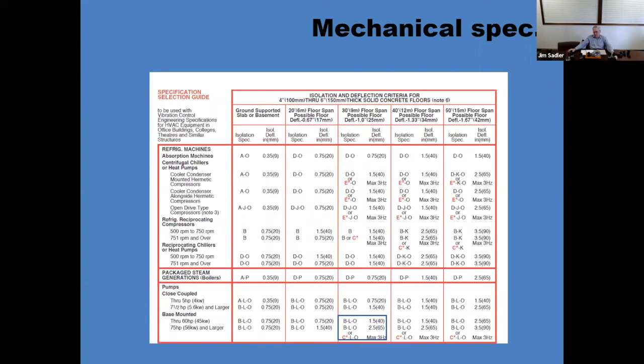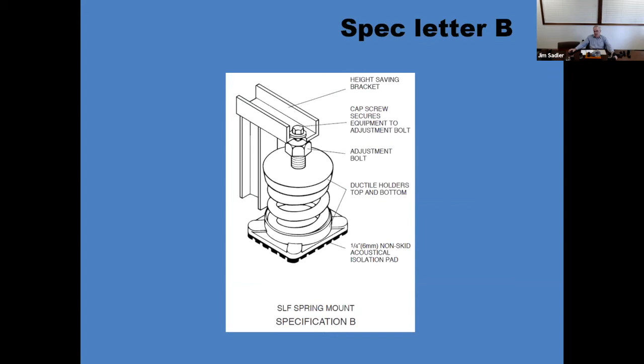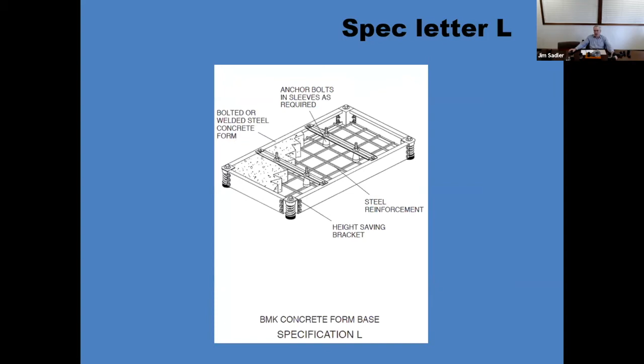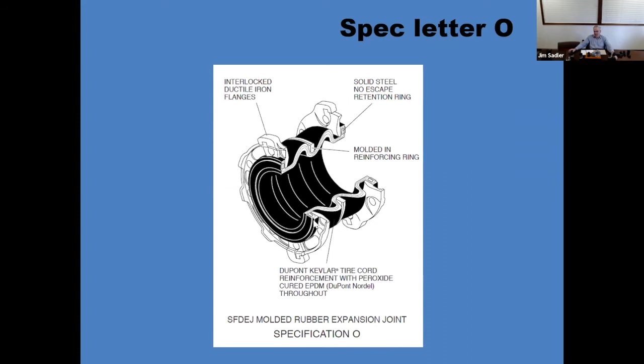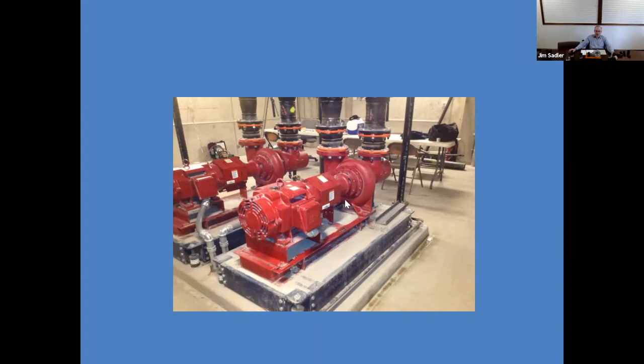So following that example through, spec letter B is a freestanding spring. Spec letter L is a concrete base. And spec letter O is an elastomeric flex connector. So here's what that would look like in the field. You have an end suction pump supported on a concrete base. The base is supported on springs, and we have flex connectors at the suction and discharge.